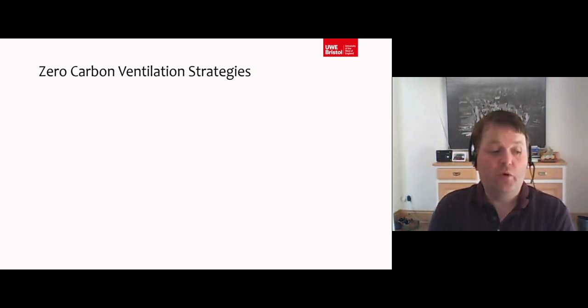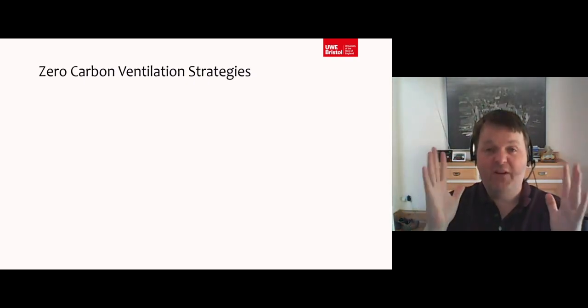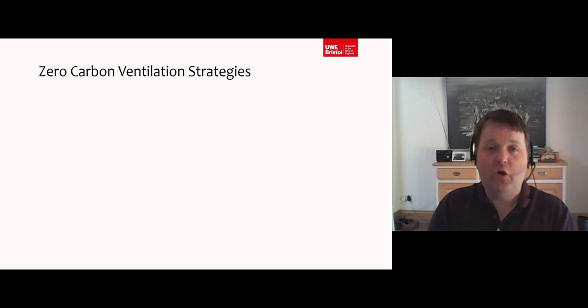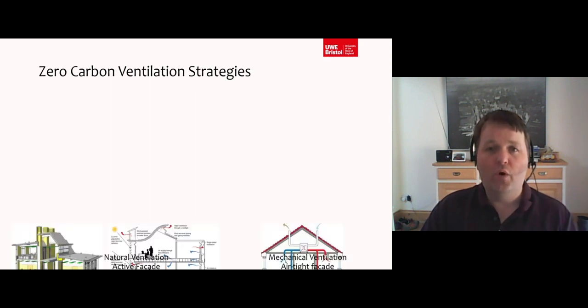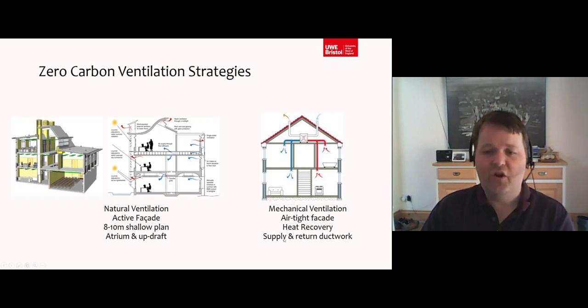So for this case study, we're going to look at a piece of equipment called a mechanical ventilation heat recovery, MVHR, which is a key part of one of the main strategies for ventilation in zero carbon buildings. Before we get into that, I want to set the context a little bit and look at the options. So there are two main options for ventilation strategies when it looks at zero carbon buildings.